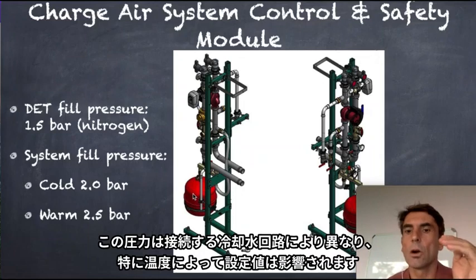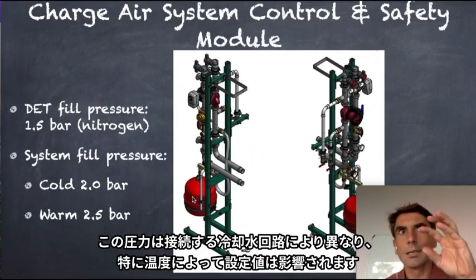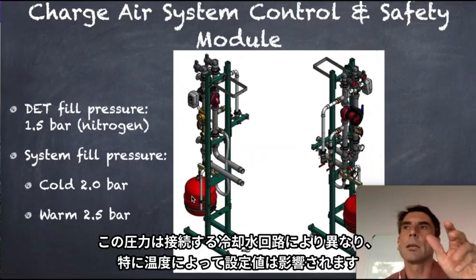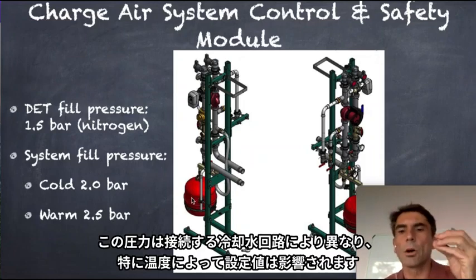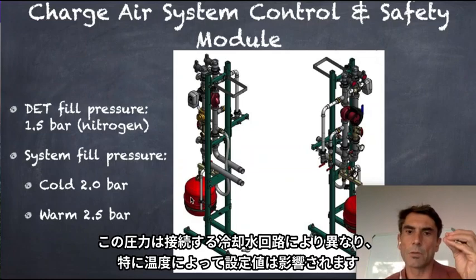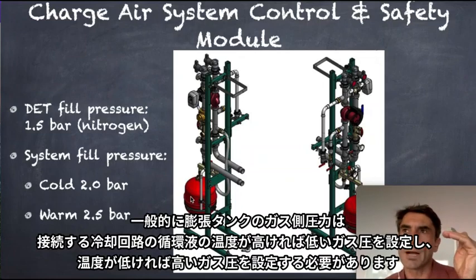Not all expansion tanks have the same pressure. It depends on the system and the volume, but on the operation temperature of the system. If you operate with a higher temperature, you have a lower pressure, usually on the gas side. If you operate with a lower temperature, you will have a higher pressure on the gas side of the expansion tank.